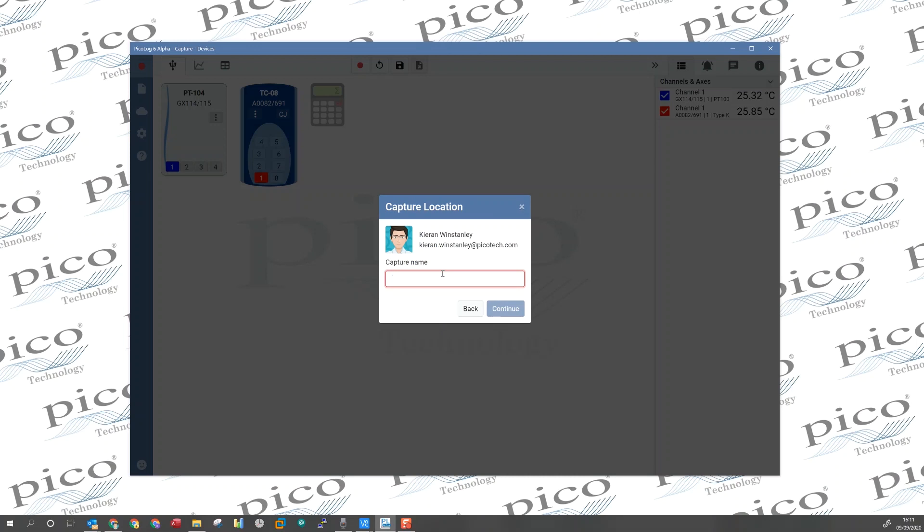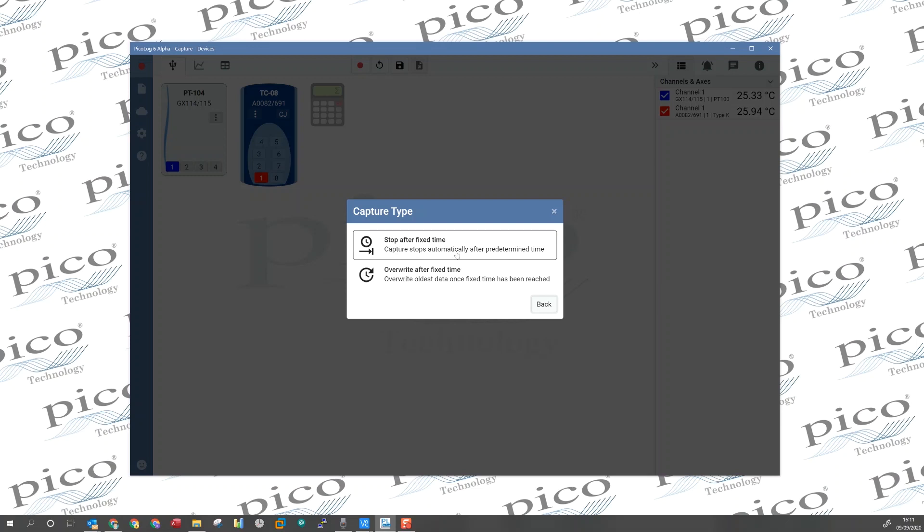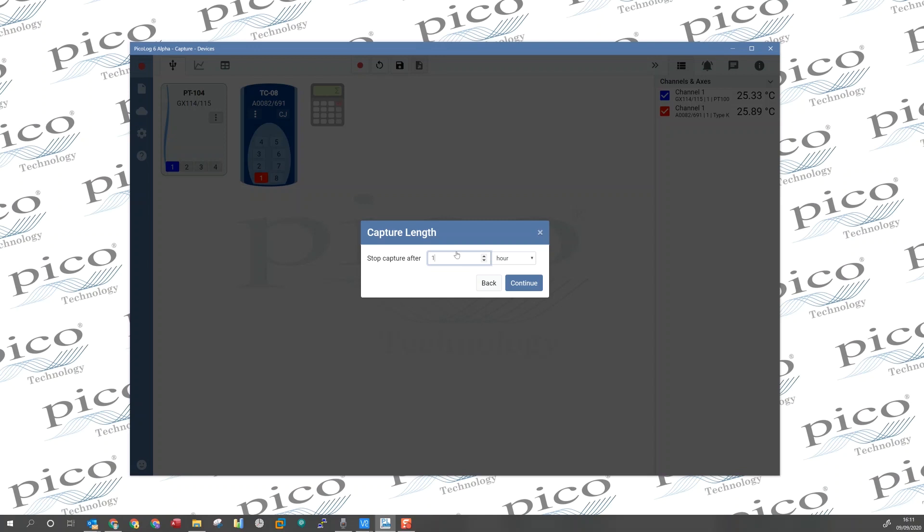And now we need to type in a capture name. My first capture. For this demonstration, I'm going to pick stop after a fixed time, but it is worth noting at this point that we've limited the maximum capture length to 30 days for this particular beta test. And the maximum sampling rate of any channel is 100 milliseconds, if that device supports it.